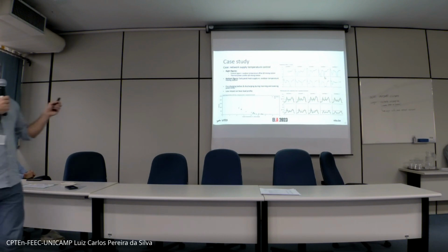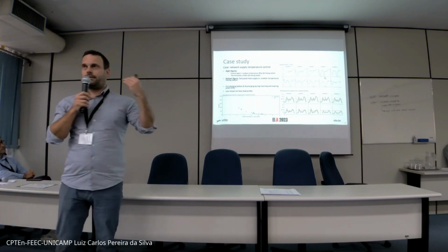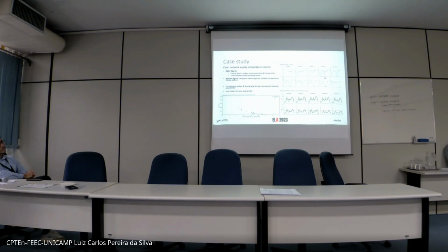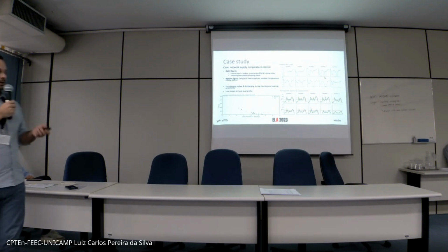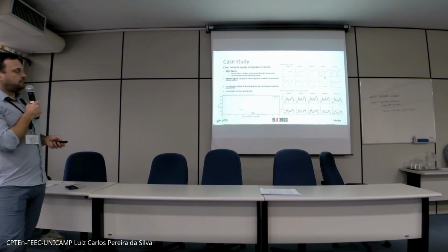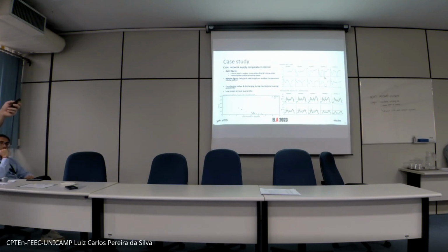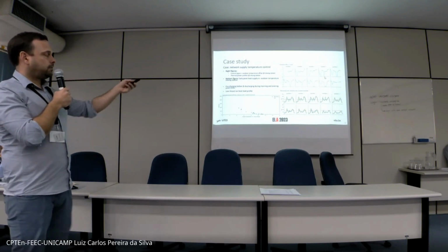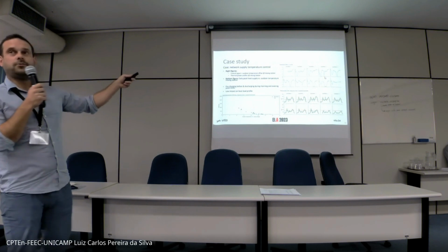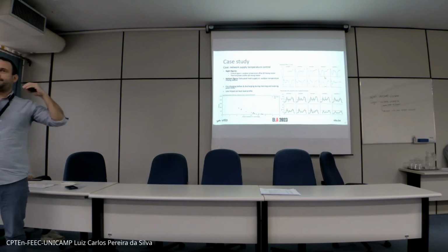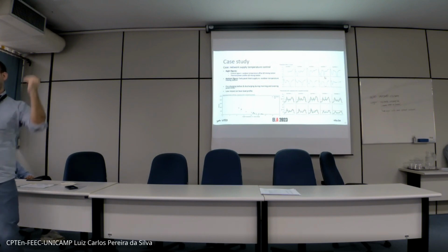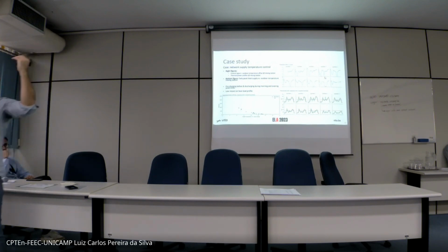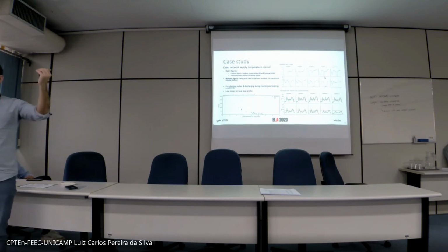The second case study is where we want to use the network as an energy storage system. Here you see the control signals, which are sensible, because what it tries to do is before the peak heat load would come, say at 6 or 7 in the morning, you see a drop, meaning the controller detects it's colder outside, so it pre-charges the network. It increases the temperature going into the network in anticipation of this peak, so when the peak is there, it would be lower.